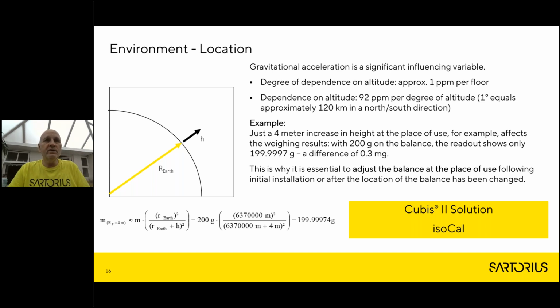In addition to this, we also have to consider the latitude of the laboratory on a global scale, because the G-force is different on different degrees of latitude. This can be adjusted at the factory, but by far the best option is to get an external trained calibration technician to adjust your balance exactly where you're going to be using it and issue a calibration certificate.